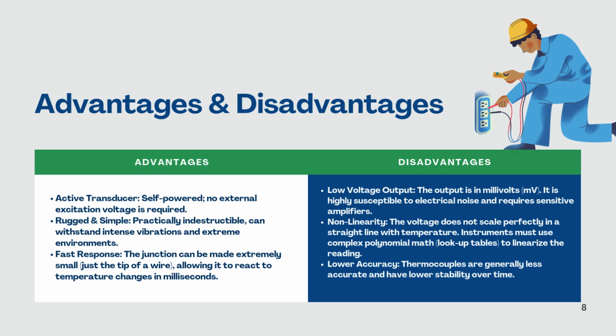Next, the disadvantages. It unfortunately has a low voltage output. The output is in millivolts, so you cannot read high voltages. It is highly susceptible to electrical noise and requires sensitive amplifiers. So it's technically not a perfect sensor to read temperatures. And next is the non-linearity. The voltage does not scale perfectly in a straight line with temperature. Instruments must use complex polynomial math or look up temperature tables to linearize the reading, which is going to be a hassle to calculate and measure the temperature.